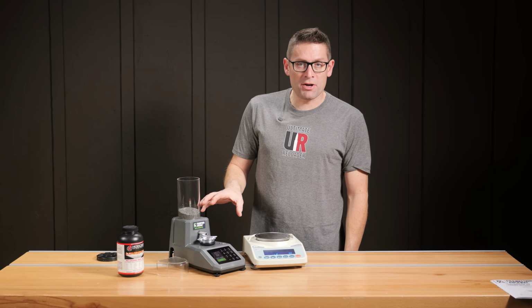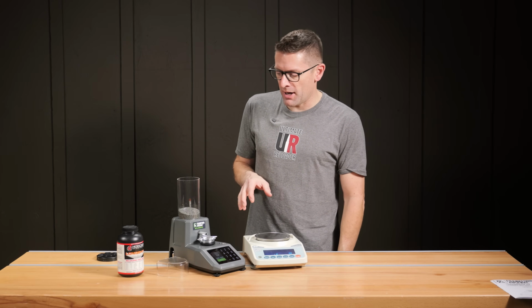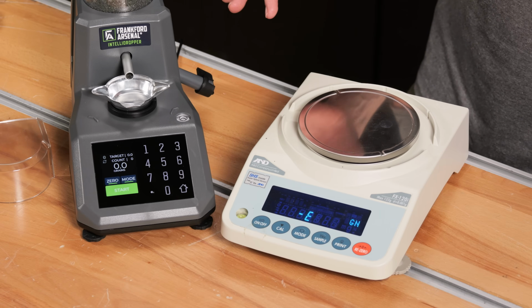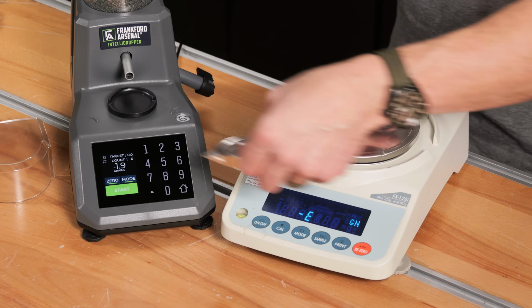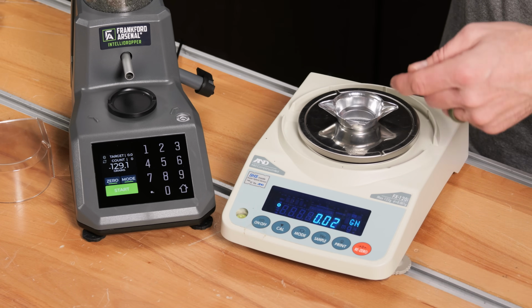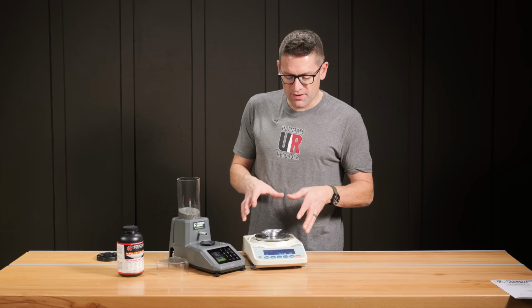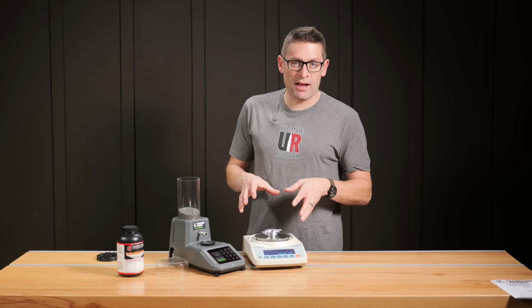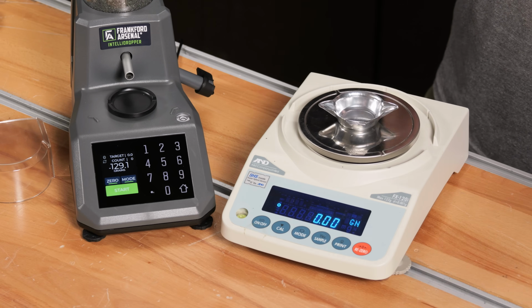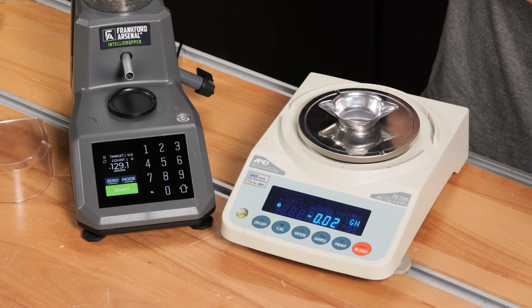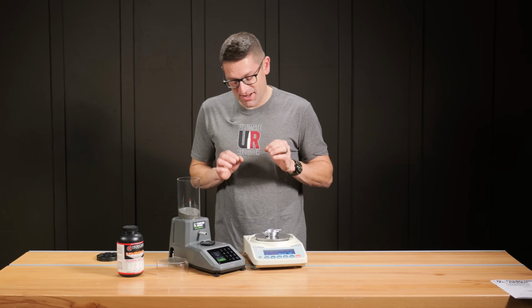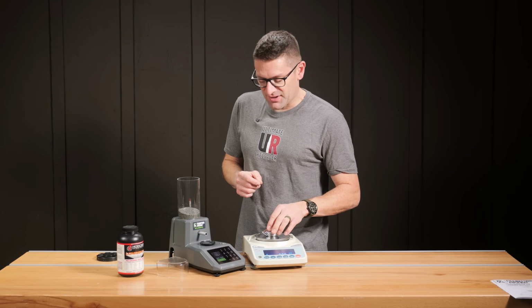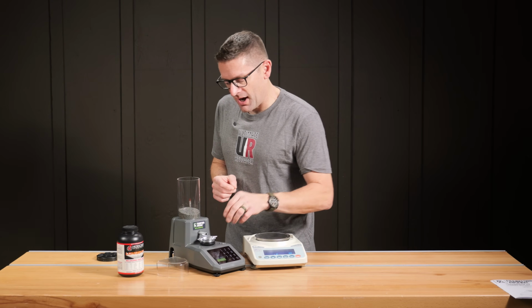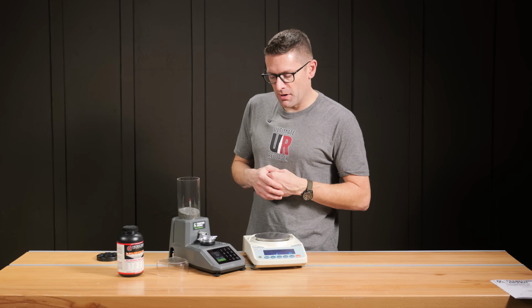So we're out of calibration mode. We've got the pan back on empty, zeroed out, and I've also zeroed out the same pan on the A&D FX 120i. This is a highly accurate laboratory balance. If we move the air, you can see how much we can influence it. This is like crazy precise. So what we want to do is just see how close we are on the scale here.